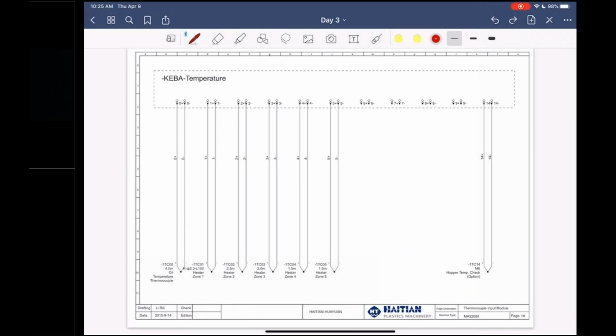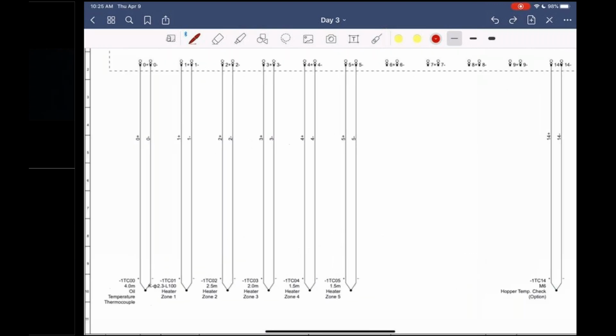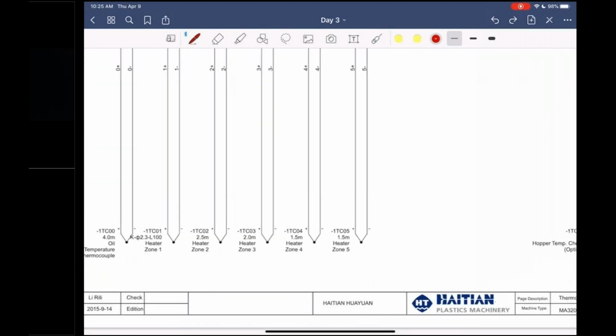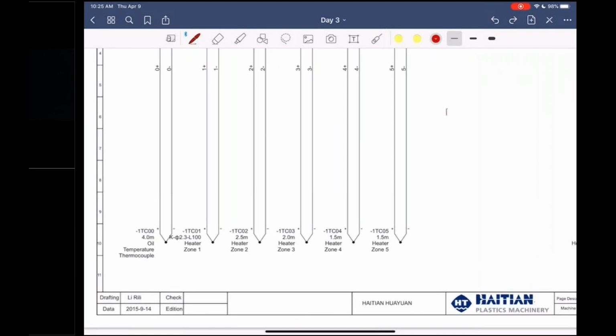This is the thermocouple layout. Again, the thermocouples are K thermocouples. If you use anything other than K, you can change it inside the controller to J or whatever other thermocouple you want to use. But K is the most accurate and has higher temperature zone ratings. And I highly recommend using just Ks.